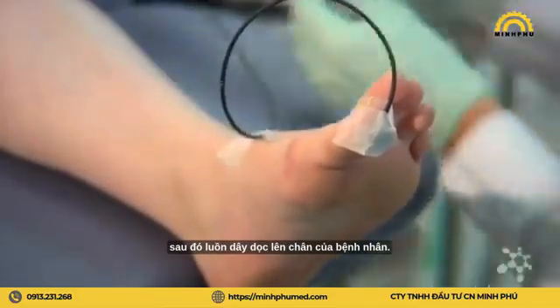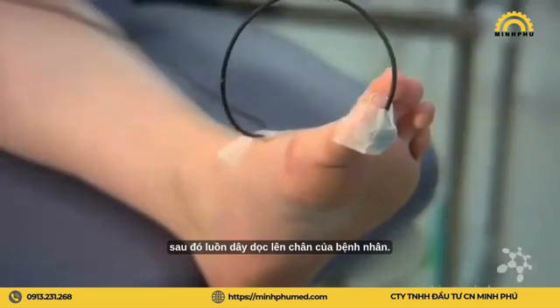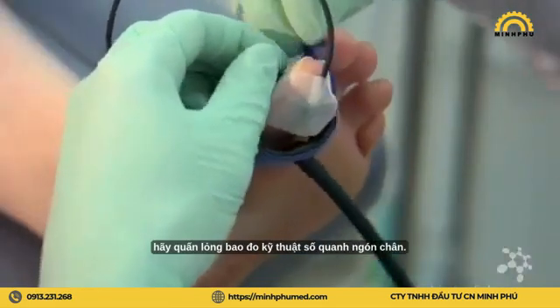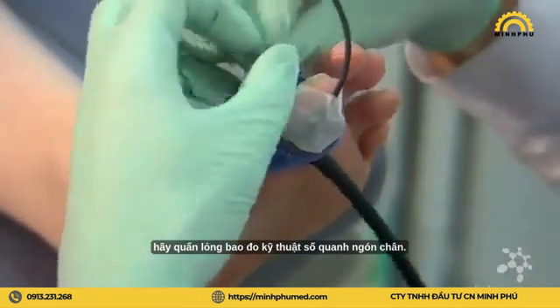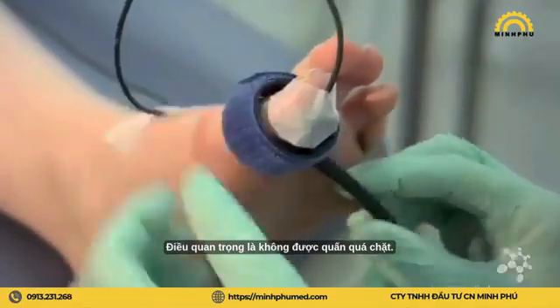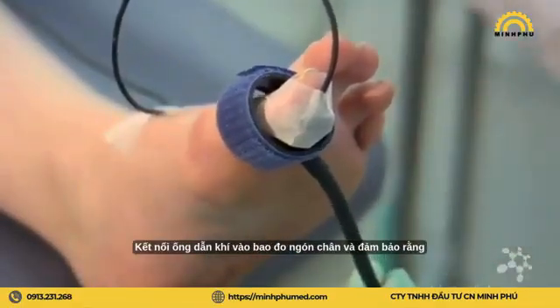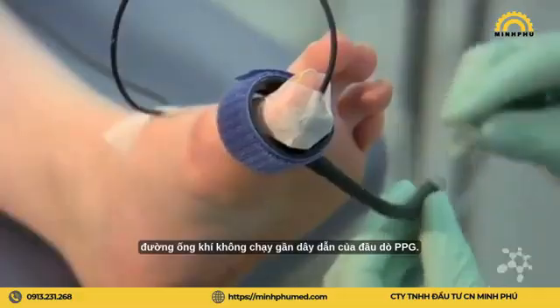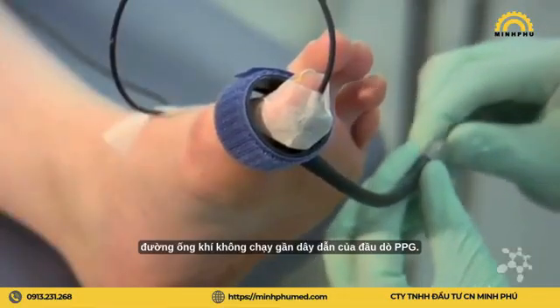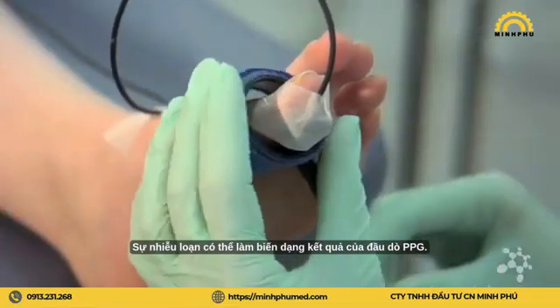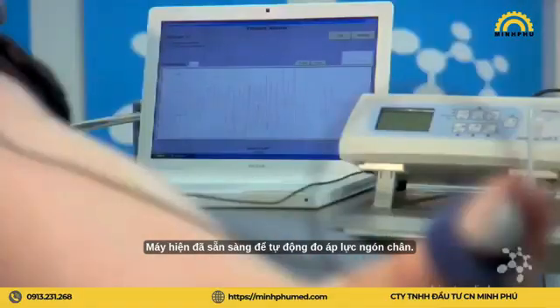Then run the wire up the leg of the patient. Once this is done, then loosely wrap the digital cuff around the toe. It is important not to wrap this too tight. Couple the air tube to the digital cuff and ensure that the air line does not run near the PPG probe wire. Interference can distort the PPG probe. The machine is now ready to automatically obtain a toe pressure.